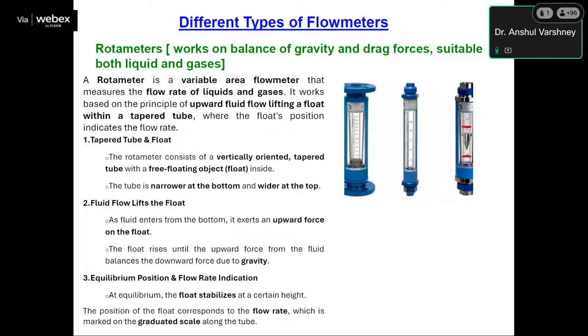Basically, it works on the balance of gravity and drag forces. It can be used for water as well as gas. These types of flow meters are also called variable area flow meters. This is basically a vertical device with a scale, and it is called a variable area flow meter because the area of the tube varies throughout the section, and there is a float inside the tube. When we start flowing water or gas, the float moves in the direction of flow, and it gives you the instantaneous flow rate.